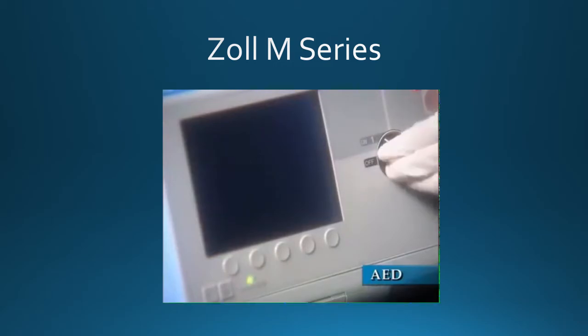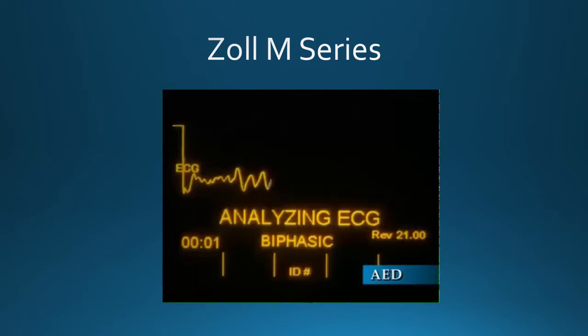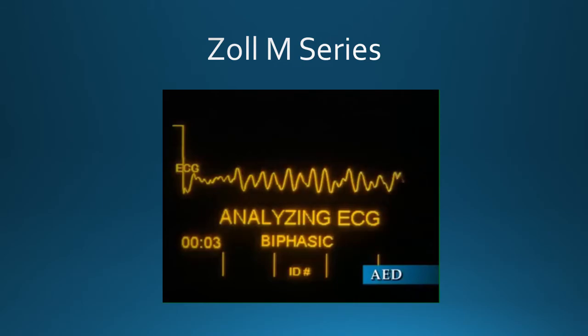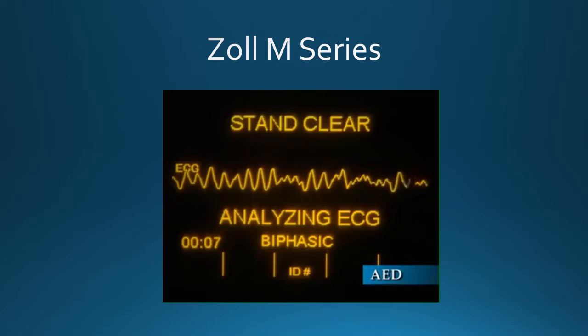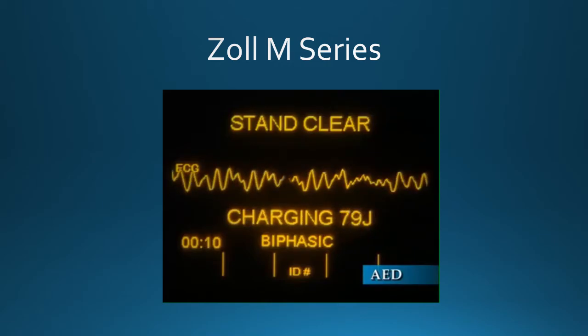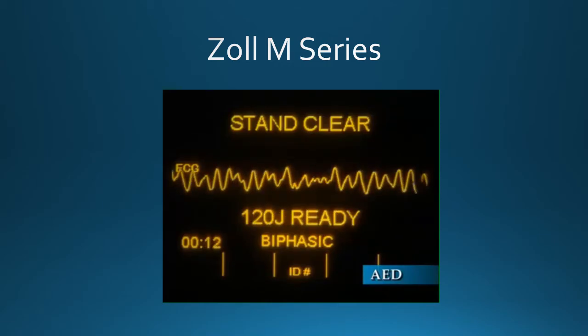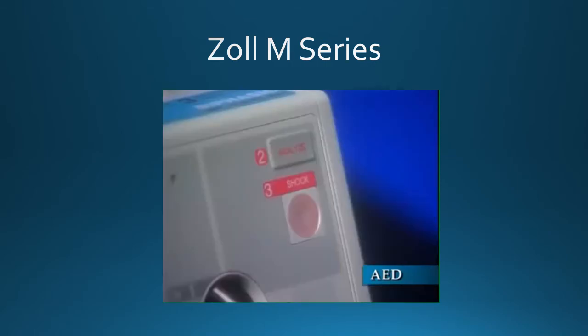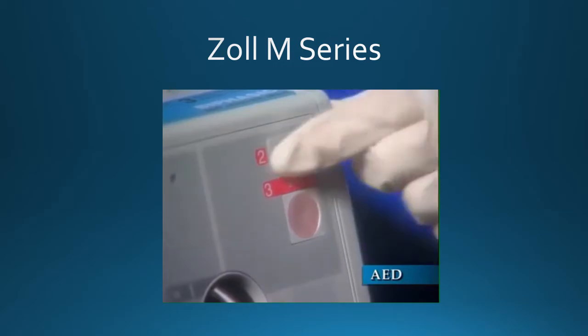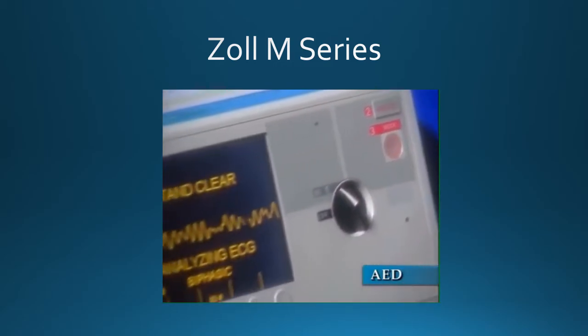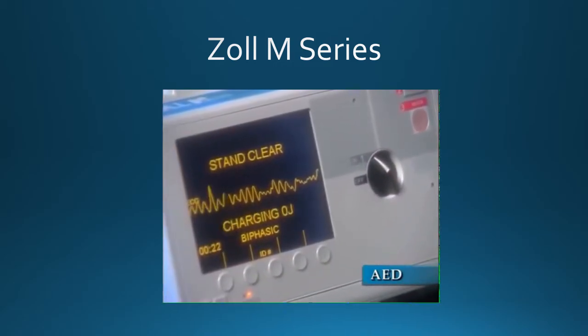To use the AED feature, the selector switch must be turned to on. The M-Series is capable of analyzing a patient's ECG rhythm in 2 different ways. Stand clear. The first is always active in the semi-automatic mode, when MFE pads or ECG cable and electrodes are in use. The second is user-activated, initiated by pressing the Analyze button.